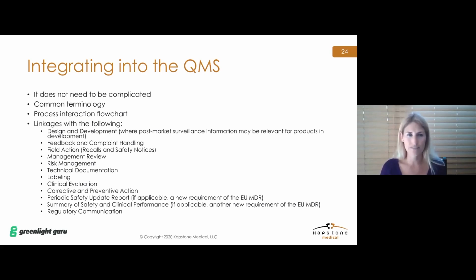Same with field actions, recalls, and safety notices. Management review. This is really taking the data that you have, perhaps your post-market surveillance report or the periodic safety update report, and feeding it back to management to make sure that they understand what's happening with the device on the market. Of course, risk management. So analyzing that data and making sure that benefit-risk determinations are updated, and any other risk management documentation is updated as required. Of course, technical documentation: any changes you make will need to be fed back into your technical documentation. Labeling, same as design and development. Are there any updates that need to occur as a result of an increased risk, a new warning, anything like that?